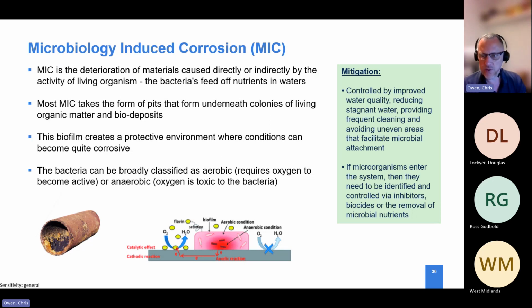And again, where you've got dead legs or changes in geometry, places where water can collect, after a period of time that water can become stagnant and it can break down, particularly if there's bacteria in the water or the water is poor quality. These produce biofilms, and underneath these biofilms we can end up with pinhole corrosion, which can take place quite quickly. And again, going back to the case study on the thin wall tube, we started to see this happen quite a lot when they were first being installed.